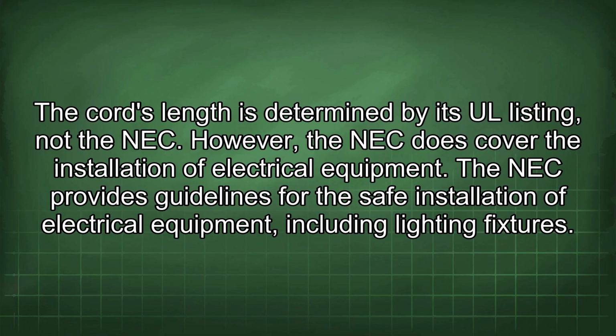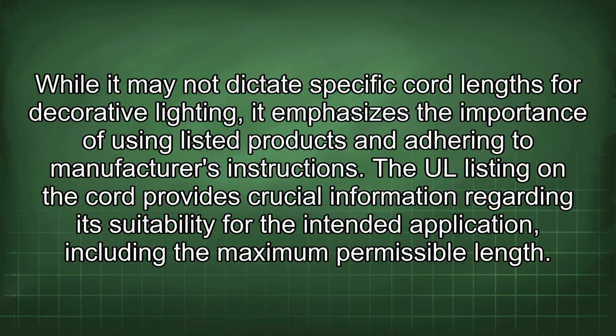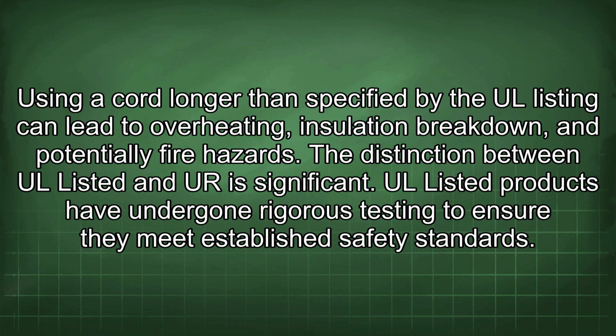However, the NEC does cover the installation of electrical equipment. The NEC provides guidelines for the safe installation of electrical equipment, including lighting fixtures. While it may not dictate specific cord lengths for decorative lighting, it emphasizes the importance of using listed products and adhering to manufacturer's instructions. The UL listing on the cord provides crucial information regarding its suitability for the intended application, including the maximum permissible length. Using a cord longer than specified by the UL listing can lead to overheating, insulation breakdown, and potentially fire hazards.